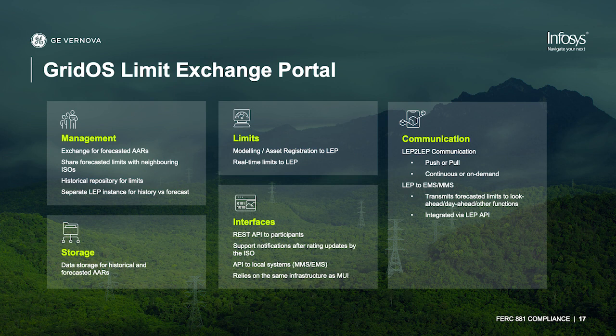Basically, it's a way to exchange your ambient adjusted ratings, or also, if you're using digital dynamic line ratings, to exchange your real-time ratings between your ISOs and TOs. It allows you to store that data for historical purposes, make sure that your limits are always in effect, and that both your ISOs and TOs, everybody, are using the same rating at the same time, so they're all controlling to the same value. We've got interfaces supported in the limit exchange portal, and also the ability to push or pull those rating sets between EMSs and market systems.